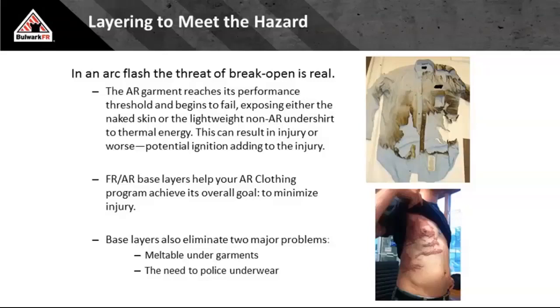So what do arc-rated base layers do? Well, first, they take away the need to inspect those white T-shirts. I don't need to know because I'm going to see that you're wearing an arc-rated base layer, because the logo is going to be right there at the neckline. Secondly, if there is break open, I've now got an additional layer of protection. So I've eliminated meltables and I've increased my protection.